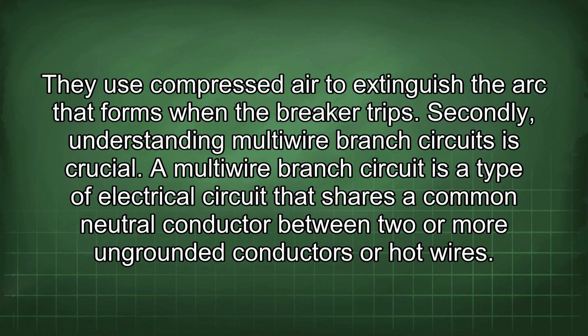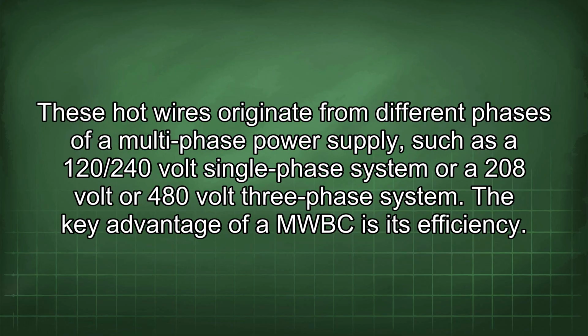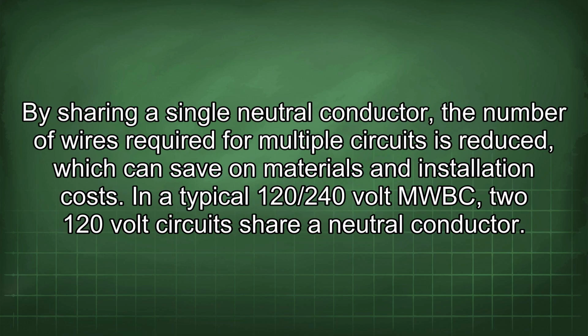Secondly, understanding multi-wire branch circuits is crucial. A multi-wire branch circuit is a type of electrical circuit that shares a common neutral conductor between two or more ungrounded conductors, or hot wires. These hot wires originate from different phases of a multi-phase power supply, such as a 120/240 volt single-phase system or a 208 volt or 480 volt three-phase system. The key advantage of a MWBC is its efficiency. By sharing a single neutral conductor, the number of wires required for multiple circuits is reduced, which can save on materials and installation costs.